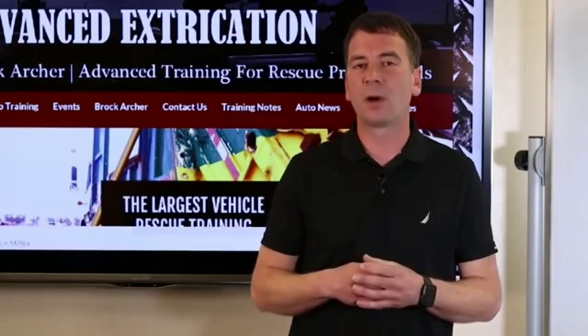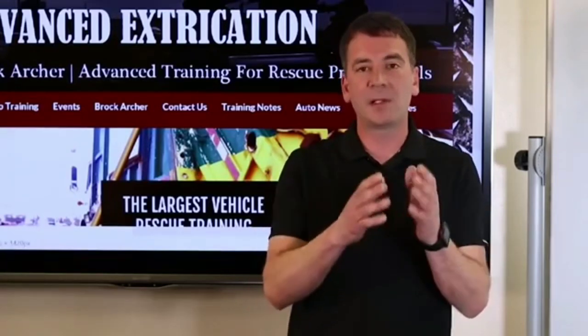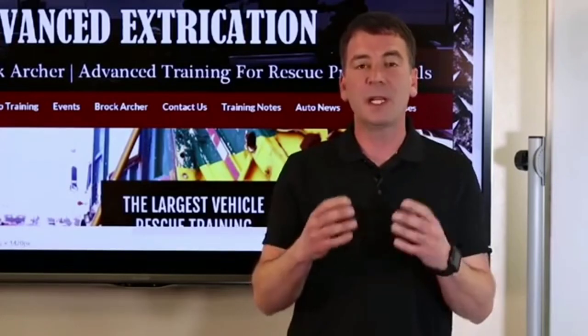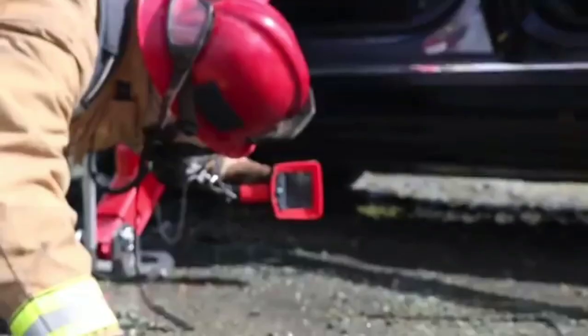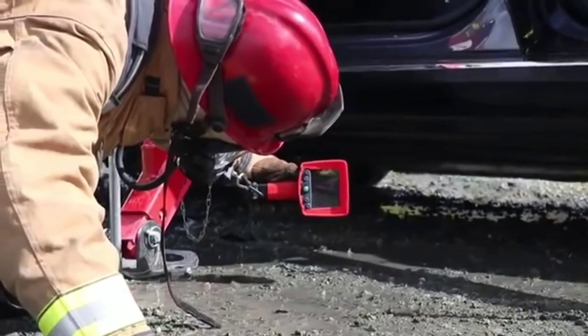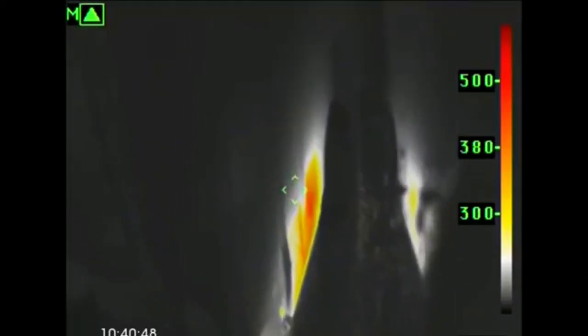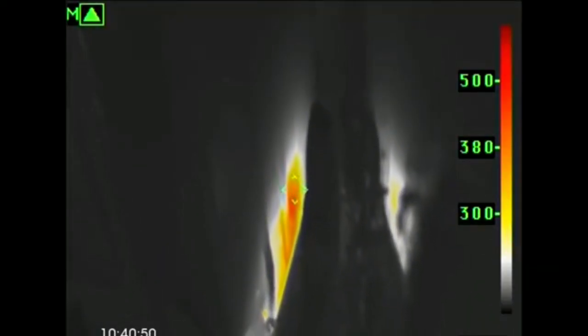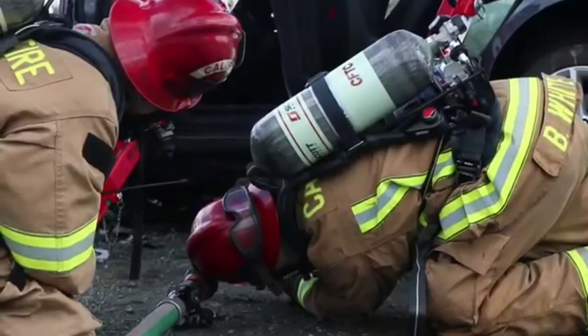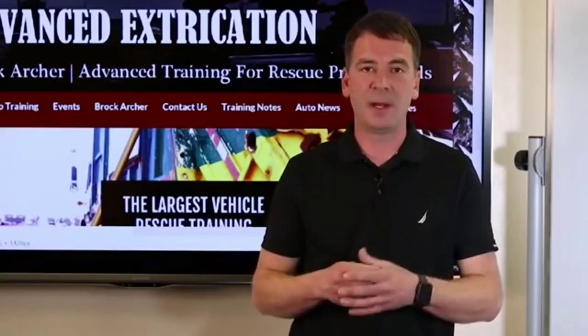The hose stream should be placed on an area of the battery where heat is determined. We can determine where the battery is heated with our thermal imaging camera, or visually by watching for areas where smoke and steam are venting from the battery.